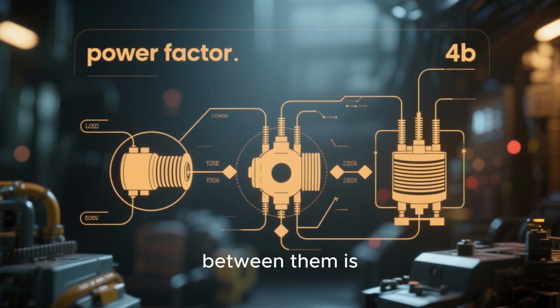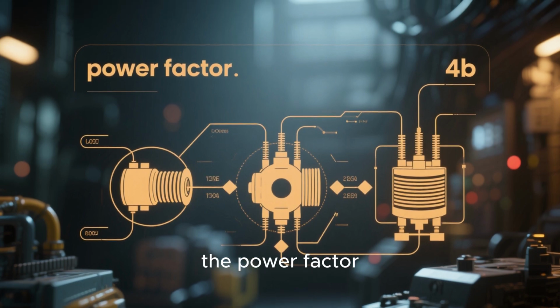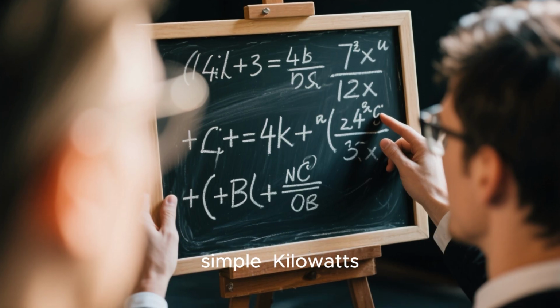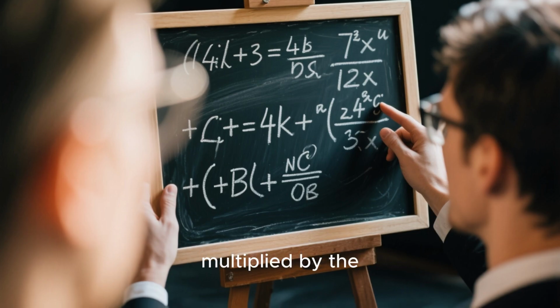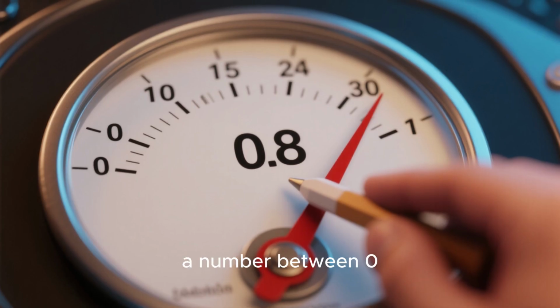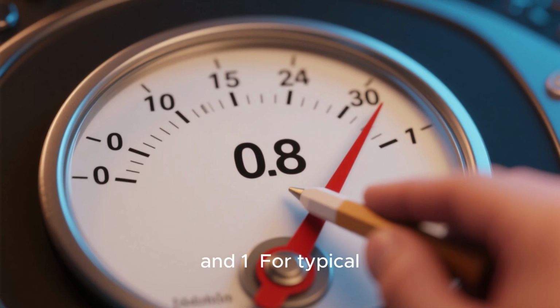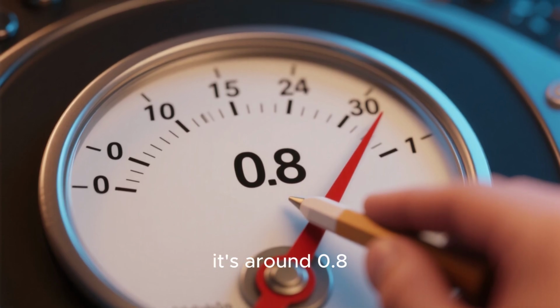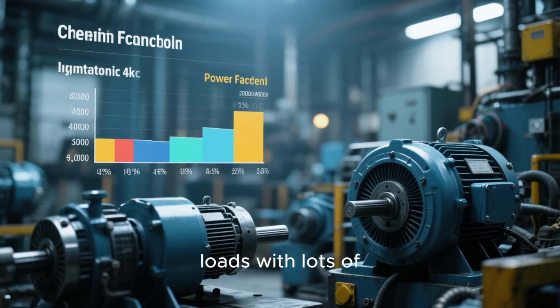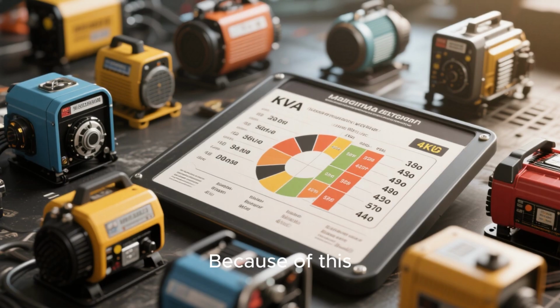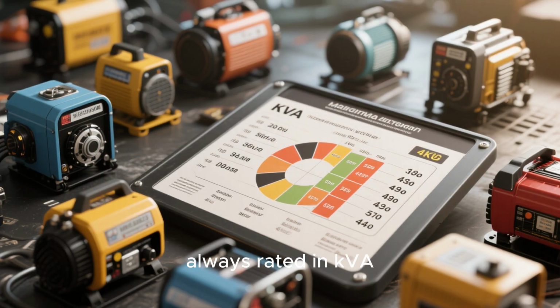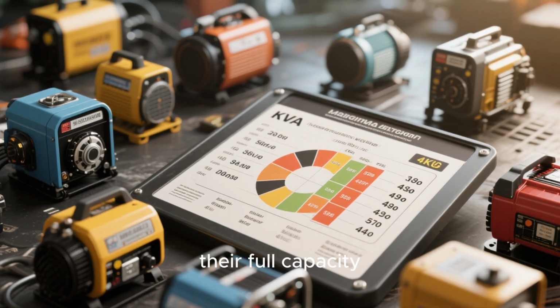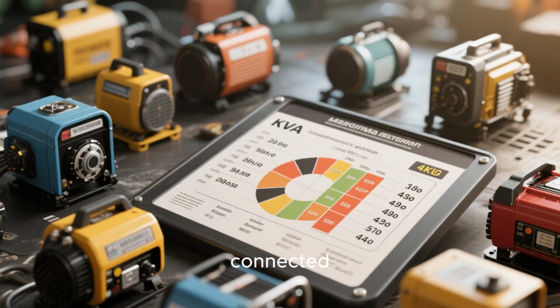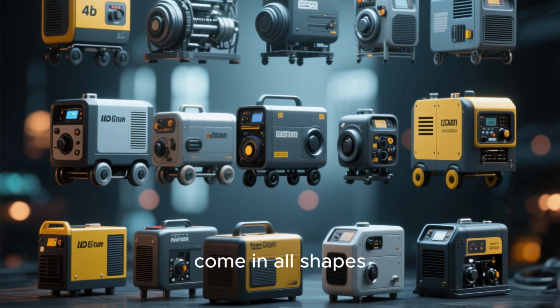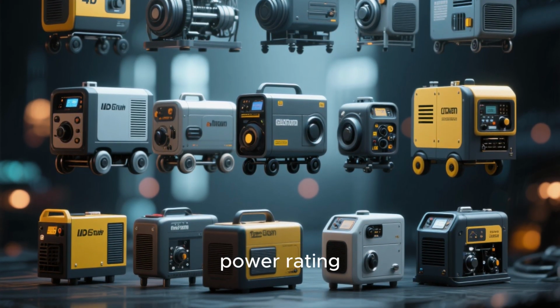The relationship between them is determined by something called the power factor. The formula is simple. Kilowatts equals kilovolt-amperes multiplied by the power factor. The power factor is a number between 0 and 1. For typical domestic loads, it's around 0.8. For industrial loads with lots of motors, it can be between 0.8 and 0.9. Because of this, generators are always rated in kVA, as it represents their full capacity, regardless of the type of load connected. Generators also come in all shapes and sizes, classified by their power rating.